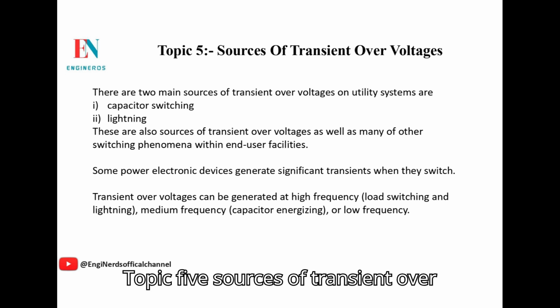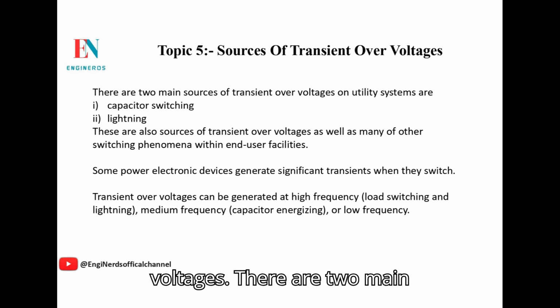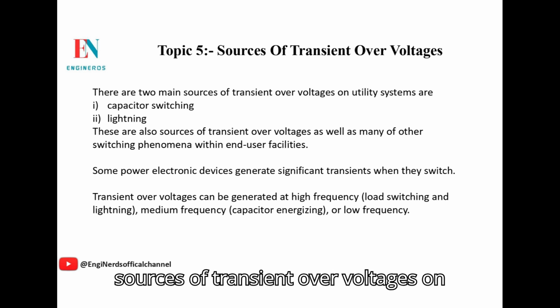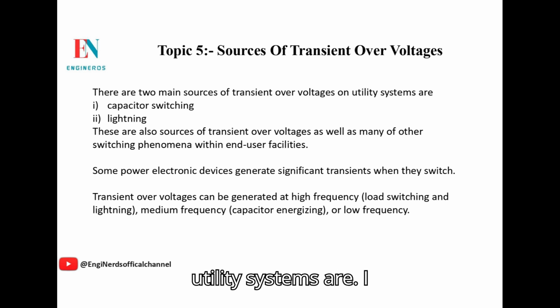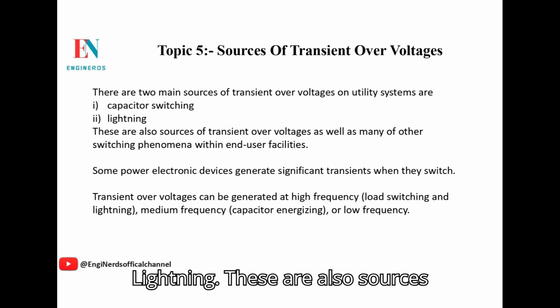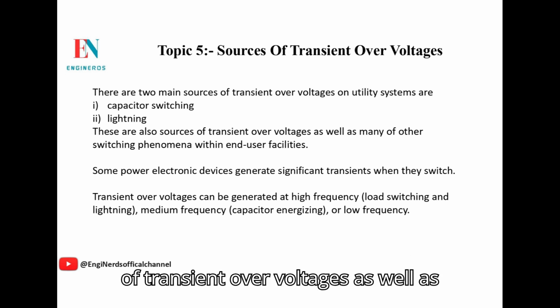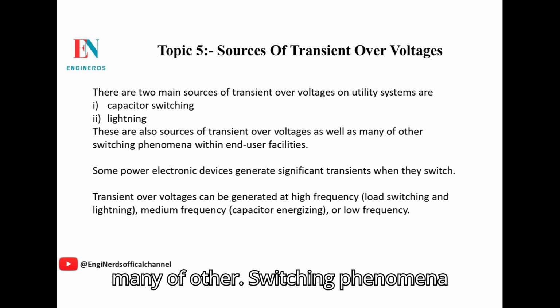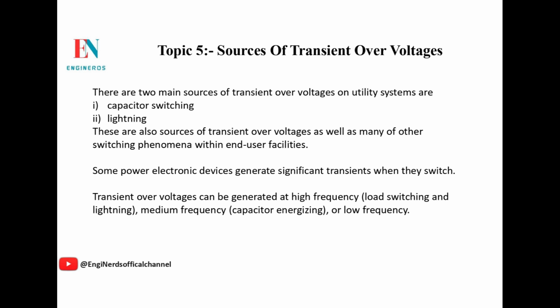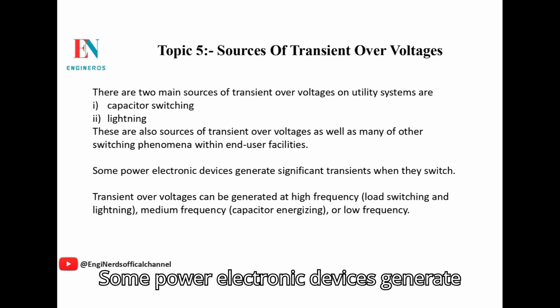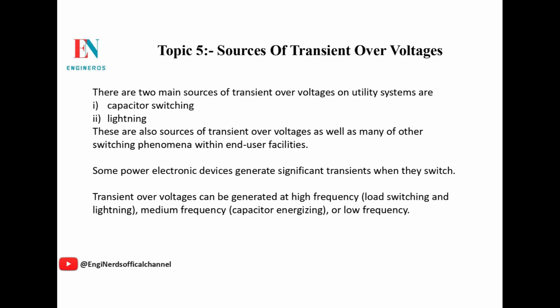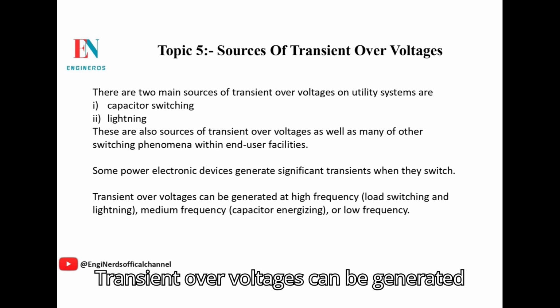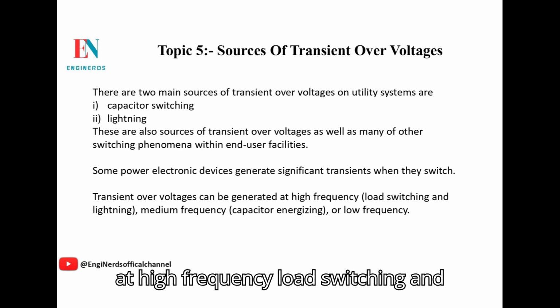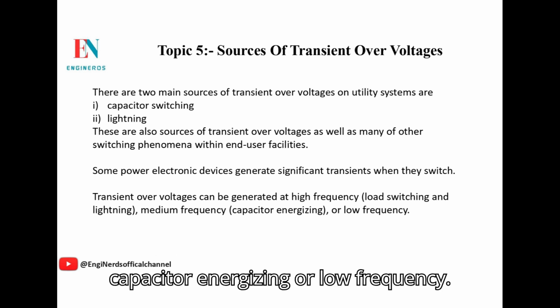Topic 5: Sources of transient overvoltages. There are two main sources of transient overvoltages on utility systems: 1. Capacitor switching. 2. Lightning. There are also other sources of transient overvoltages, such as many switching phenomena within end-user facilities. Some power electronic devices generate significant transients when they switch. Transient overvoltages can be generated at high frequency, load switching and lightning; medium frequency, capacitor energizing; or low frequency.